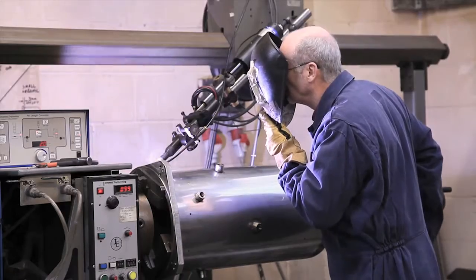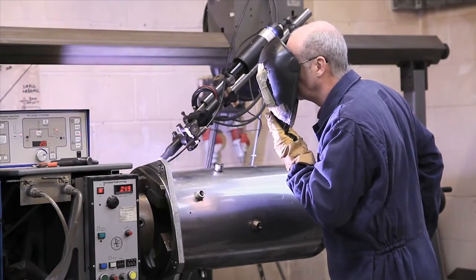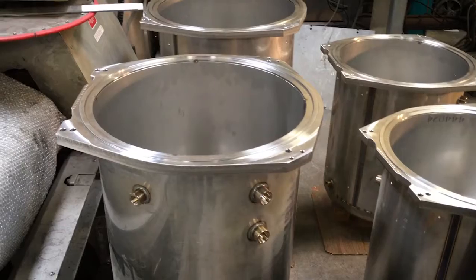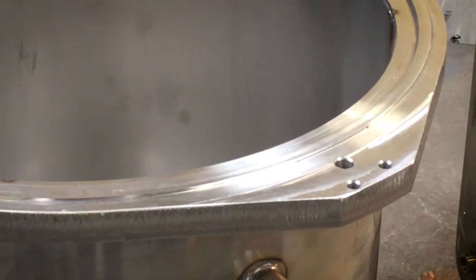To finish the pressure vessel, a stainless steel header plate is welded to the open end of the cylinder. The header plate incorporates mounting flanges used to mount and fix the pressure vessel to the autoclave door and the mounting frame.